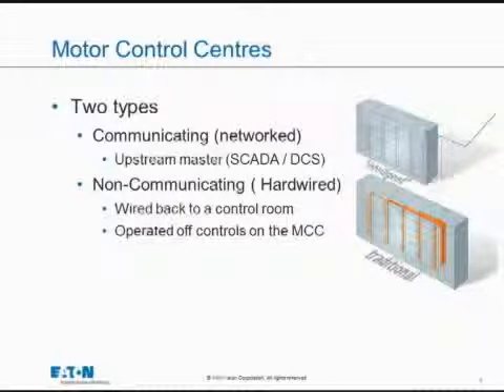And then you're dealing with non-communicating or hardwired MCCs, which are typically wired back either directly to a panel somewhere on the plant floor, which has a PLC in it, and that in turn takes those signals, digitizes them, and sends them up to the SCADA system. Or they may be hardwired back to a control room somewhere, or even hardwired back to actually controls on the MCC bucket itself. All of those are very, very common.